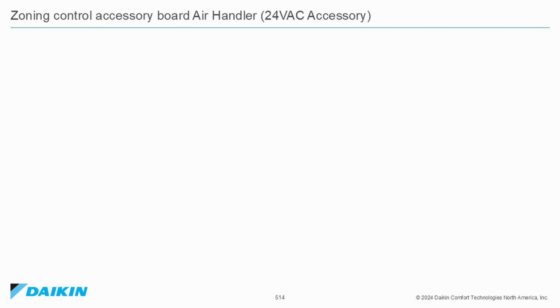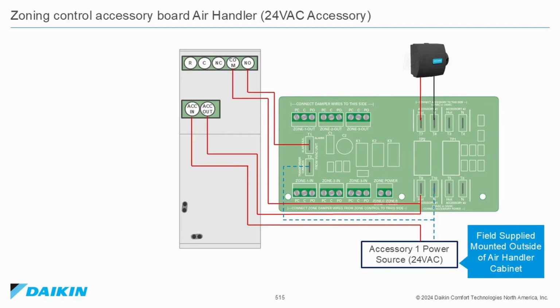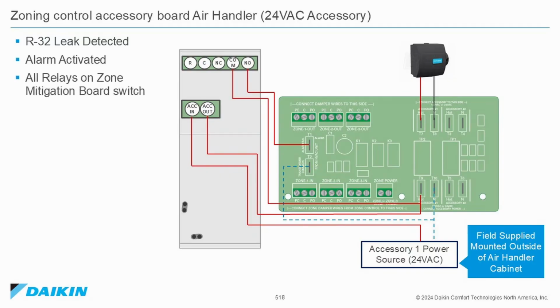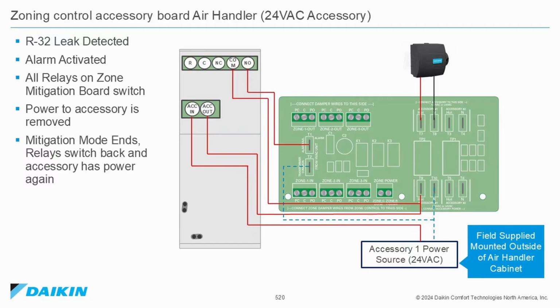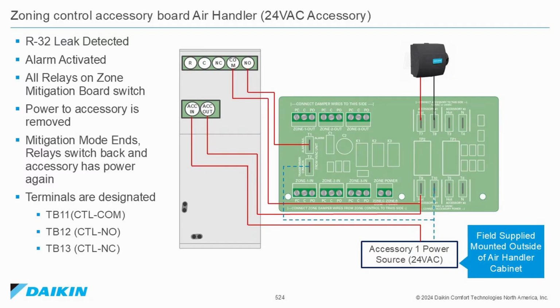Zoning control accessory board, air handler for 24-volt accessory. R32 leak detected. Alarm activated. All relays on zone mitigation board switch. Power to accessory is removed. Mitigation mode ends. Relays switch back and accessory has power again. The terminals are designated TB11, common, TB12, normally open, TB13, normally closed, with a field-supplied transformer mounted outside the air handler cabinet.